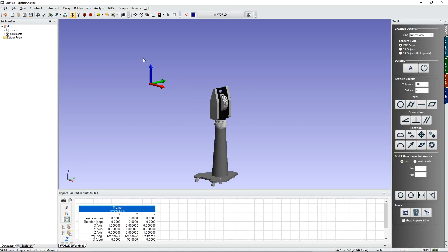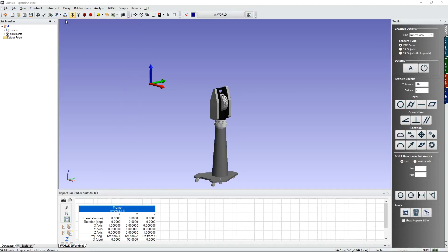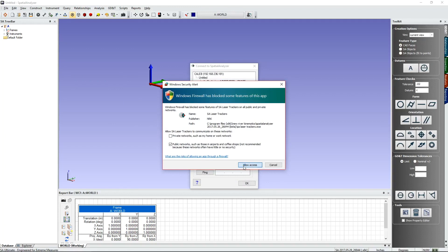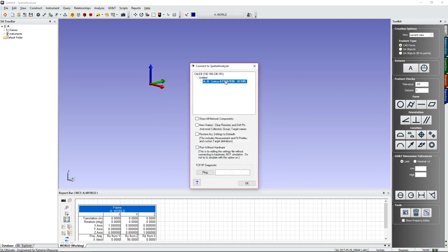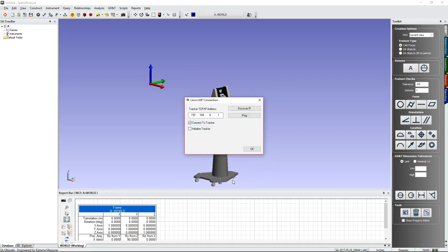Once the instrument is added to the job file, connect to it using the running man icon for the Run Interface. Select Laser Trackers — if your firewall restricts access you may need to approve that — then select the tracker to connect to. For training purposes I won't connect here, but when running an actual tracker you'll obviously want to leave that checked.